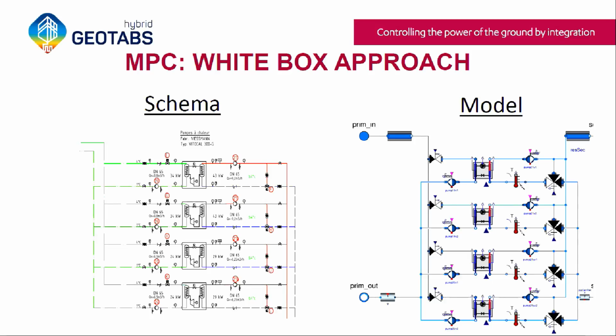The parameters we have to give are valve characteristics, heat pump characteristics, pump characteristics, and pressure drops in the system. If we know all this, we can give this information to MPC, and MPC can optimize each component, the actual opening of the valve, taking into account not only the effect on the COP of the heat pump because the temperature is going to be different, but also the pressure drop of the pump. So we can optimize the heat pump in combination with the circulation pump.